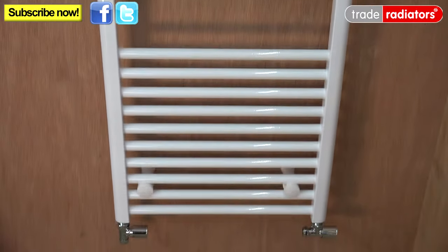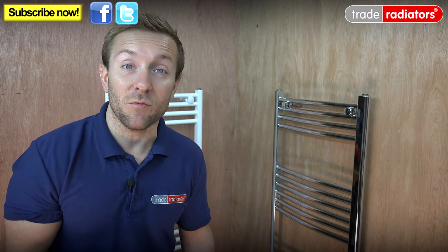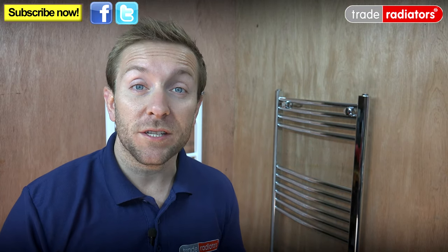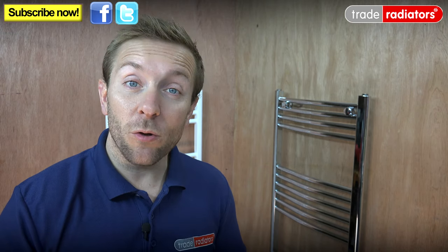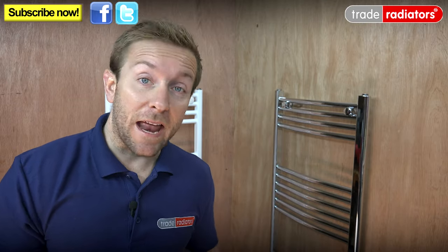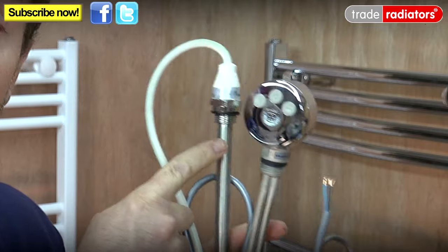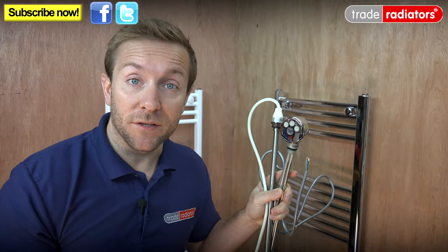All the towel rails in our value range can be dual fuel with an electric element in the bottom as well. Our value range of radiators are standard for your typical wet hot water system, with pipe centers typically 50 millimeter less than the radiator width — but be sure to check that before installing. These radiators can be electrically heated with an element; just like these two here, you've got a thermostatic one here or just a standard preset temperature one, and both of these can be controlled by remote timers as well.